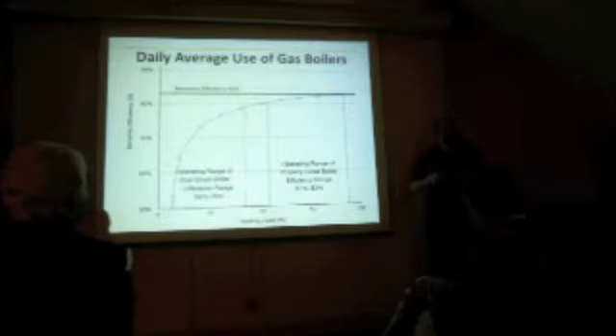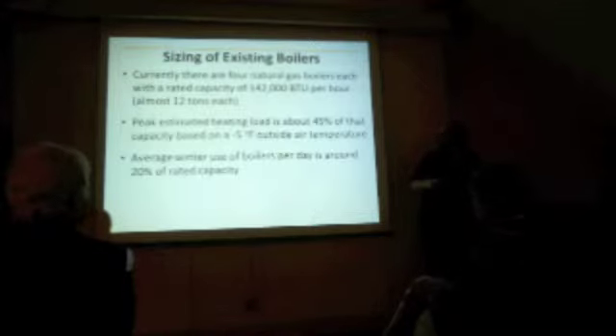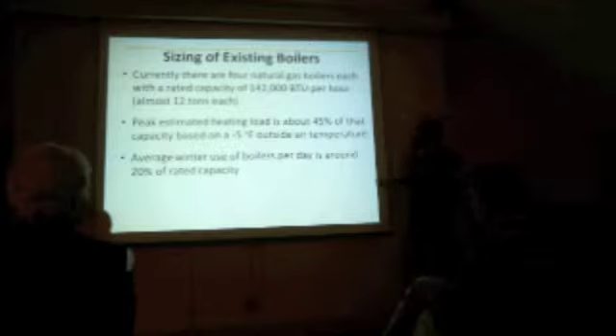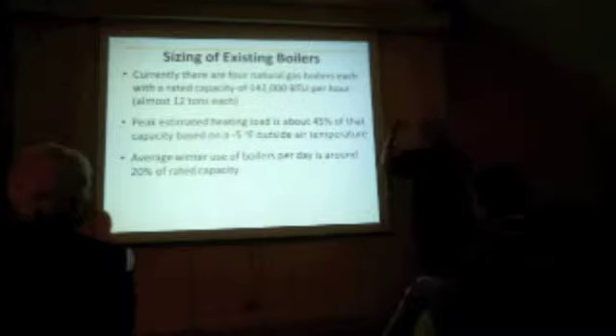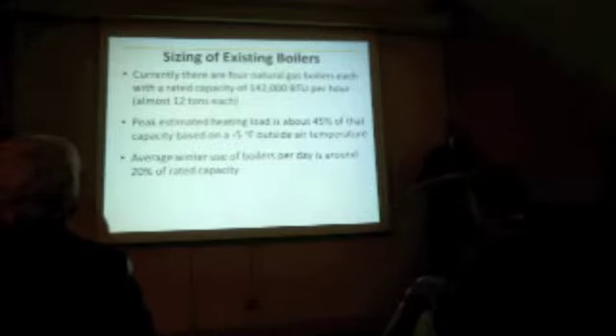Do we need 4 boilers? No, I mean, that's quantity. Yeah, right now having 4 boilers, even on the worst day, which is what we'll say here. So even if you look at what is considered your design load, what I showed you before was the average use throughout the day. Even if you take the design temperature, which for us is around -5 degrees Fahrenheit outside, even then you're only approaching 45% of the capacity of those 4 boilers. And the average over the whole winter is around 20% of capacity over the whole heating season.